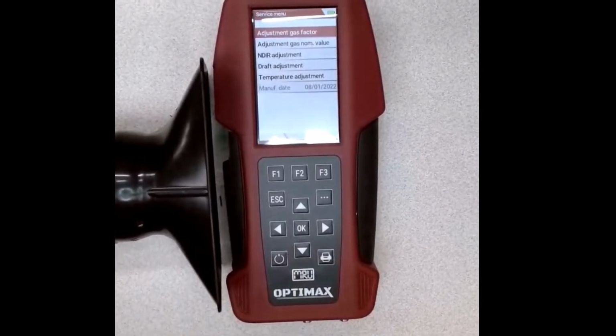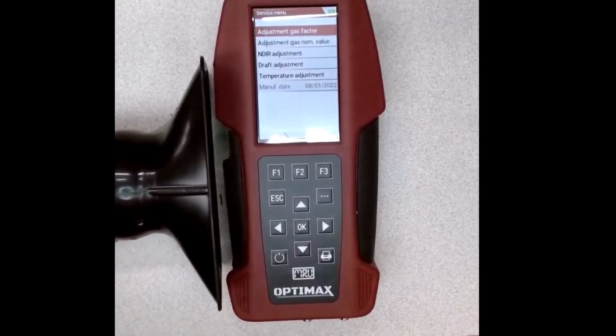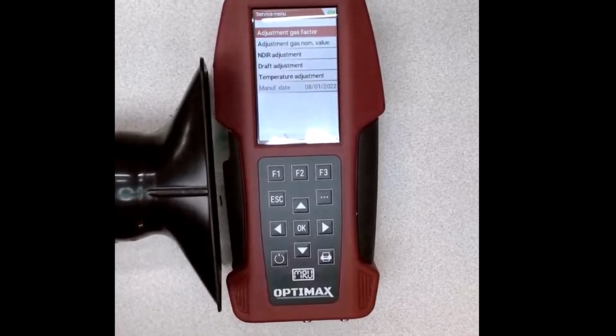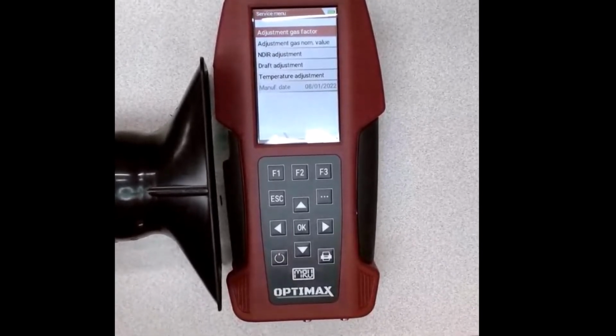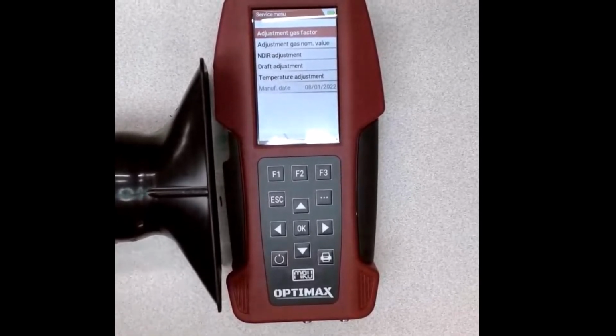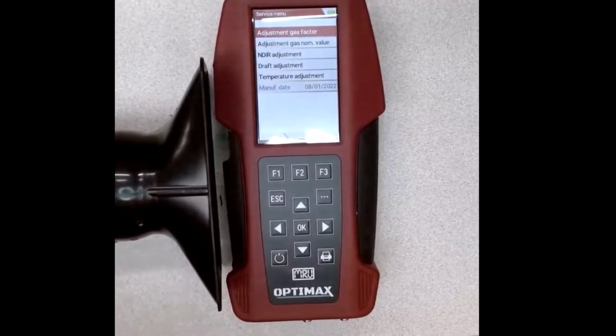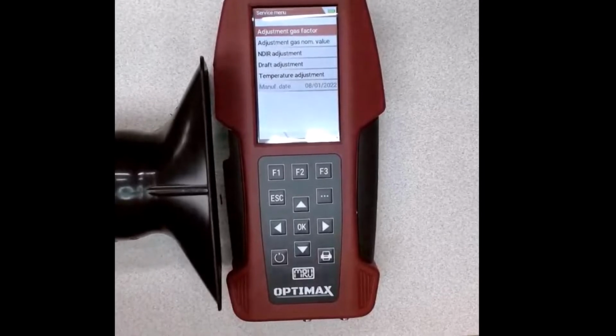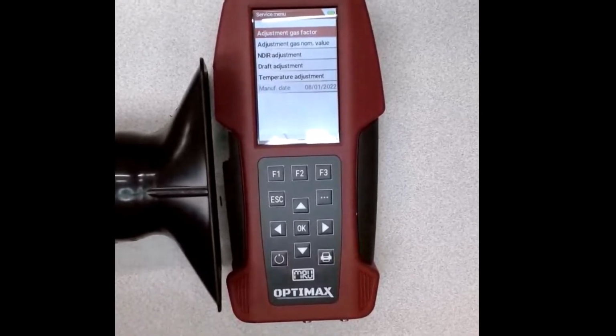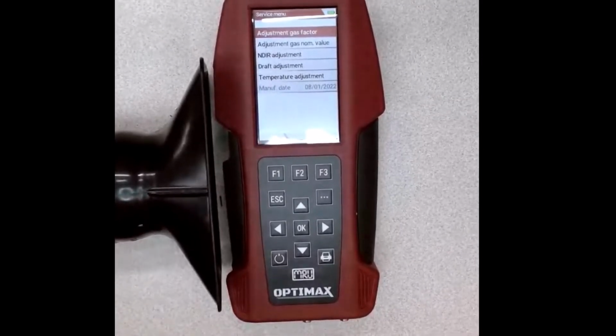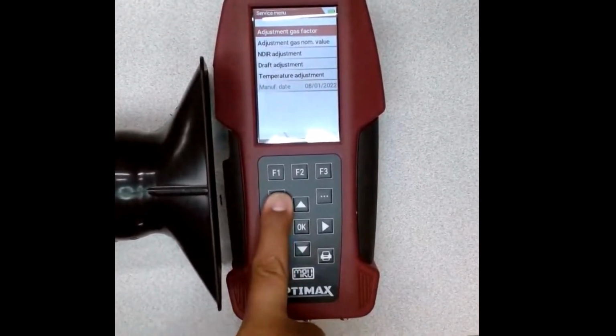You can see a lot of different adjustment options: gas factor, adjustment gas nominal value, NDIR adjustment, draft adjustment, temperature adjustment. We'll be working with just two of these, and that will be the nominal value and the NDIR. The nominal value menu will open up to calibrate the electrochemical sensors, the oxygen and the H2S, and the NDIR adjustment will open up the adjustment for the infrared for the CO2 and the methane. So we'll use those options. We'll have to come back to them though, because we're going to exit out of this menu just one more time.